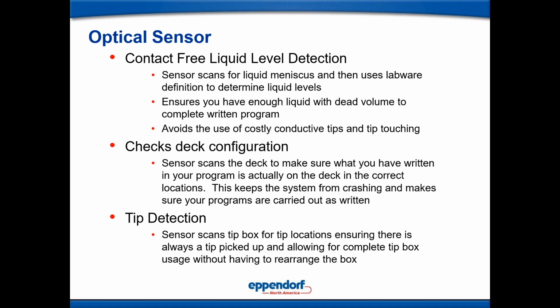Most machines, when you have an application where you need to know the liquid volume there, have to attach a conductive tip. The conductive tip pierces the surface of the liquid, and then it senses a change in electrical impedance, and it says, okay, you're in the liquid here. All right, at this point, you're in the liquid. And then it can figure out, it will work from that. But our machine goes way beyond that, okay?